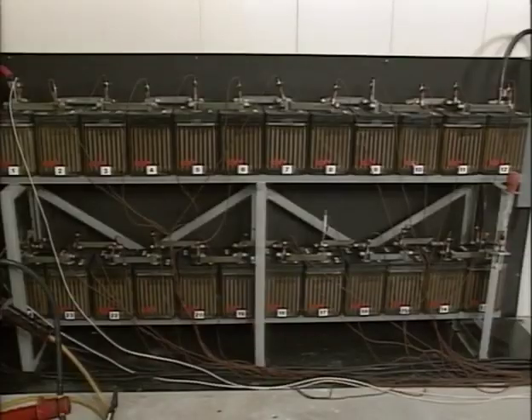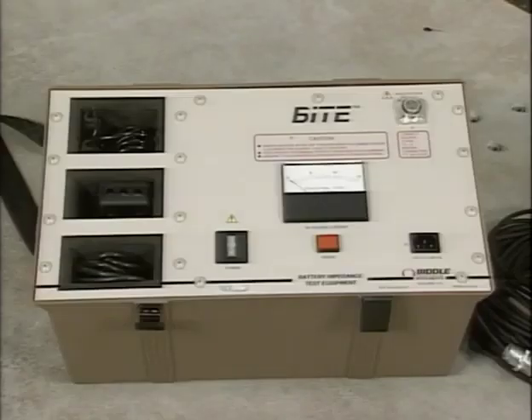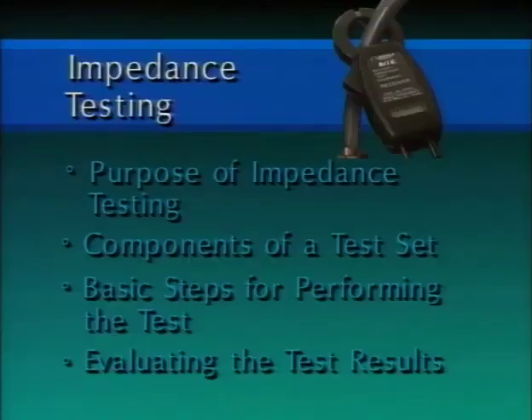Capacity testing is a proven way to determine the remaining useful life of a battery, but excessive capacity testing can shorten the life of the battery. For this reason, capacity testing is only done about every 5 years. Between capacity tests, the remaining life of the battery can be assessed with impedance testing. This last part of the program will describe battery impedance testing.